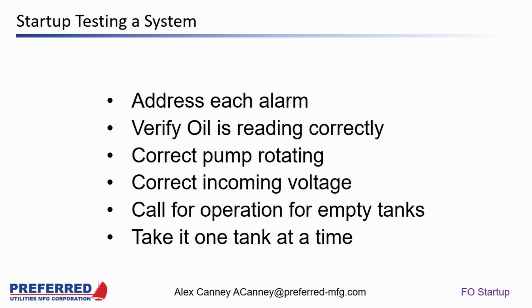It wasn't until we actually started putting oil into the day tanks that we found out the continuous level sensors used for indicating digital gallon level were not wired properly by the electrician. We were filling day tank 1, but it was showing as day tank 3. All we had to do was switch the wiring in the control panel to make it work properly.